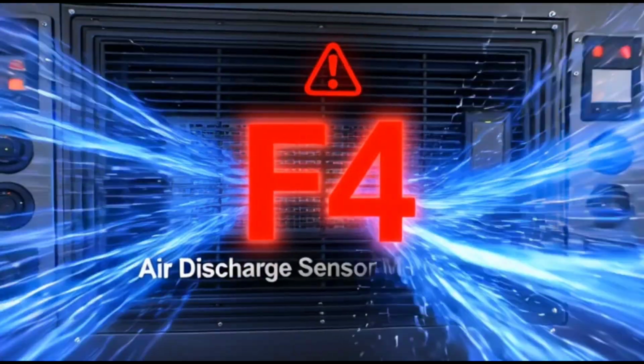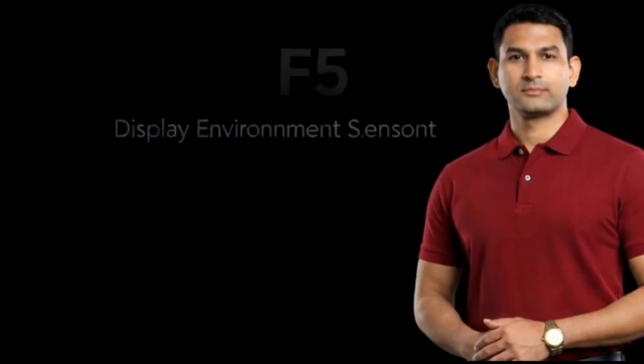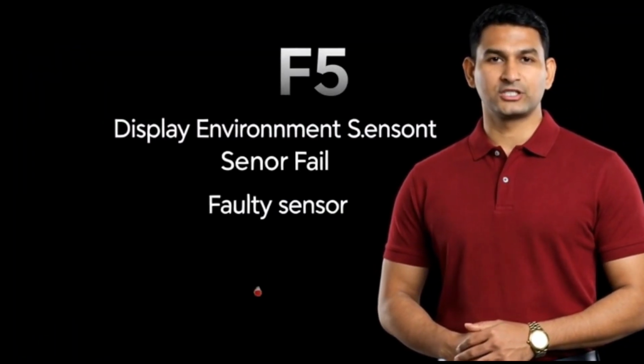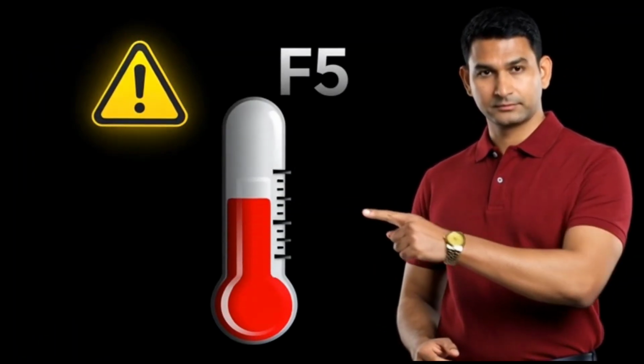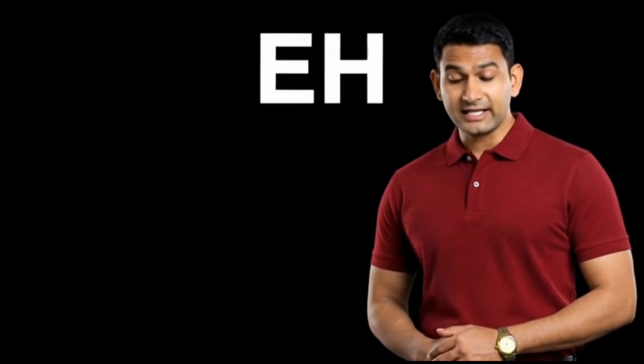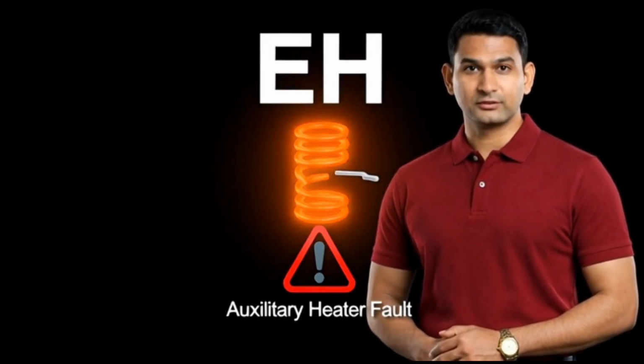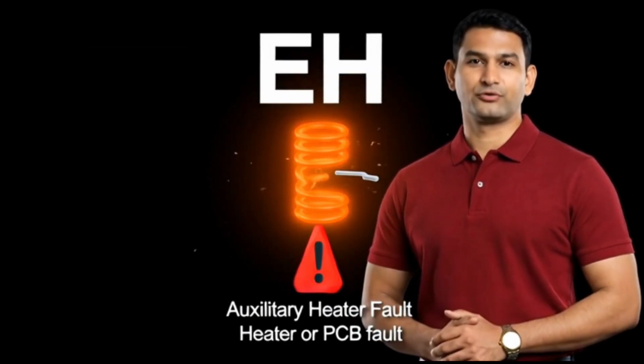F4 indicates a malfunction in the air discharge sensor. This is a sensor issue. F5 shows that the display environment sensor is faulty. EH indicates a problem with the auxiliary heater. It could be a heater or PCB fault.